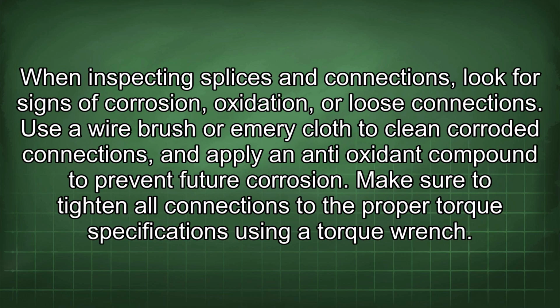When inspecting splices and connections, look for signs of corrosion, oxidation, or loose connections. Use a wire brush or emery cloth to clean corroded connections and apply an antioxidant compound to prevent future corrosion. Make sure to tighten all connections to the proper torque specifications using a torque wrench.